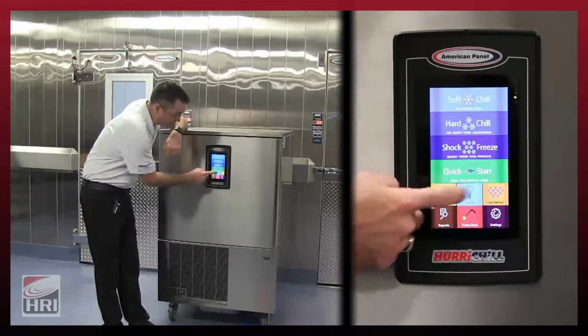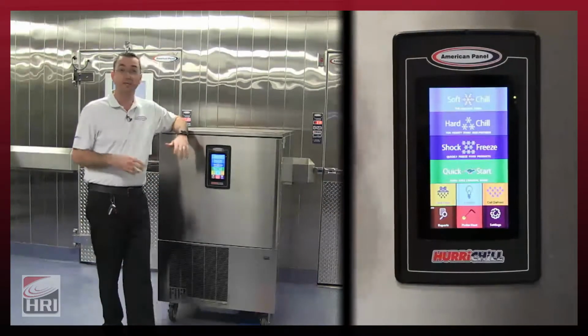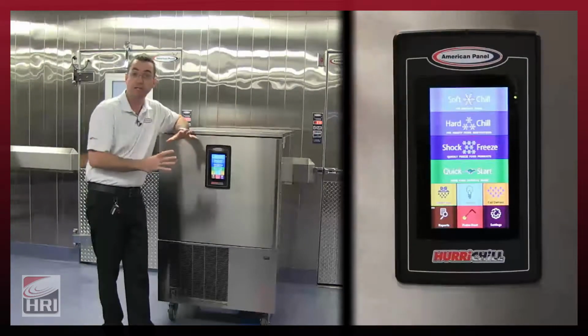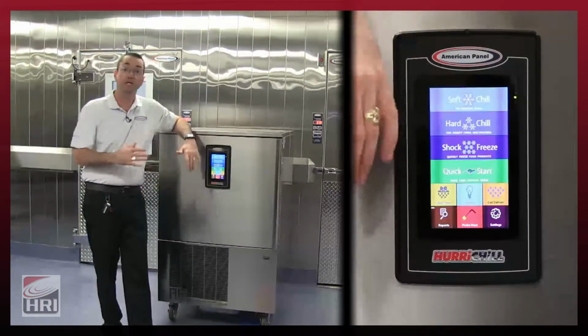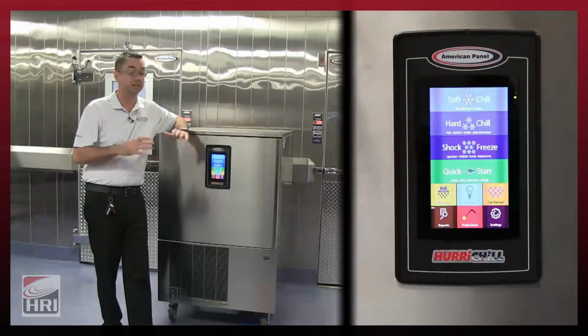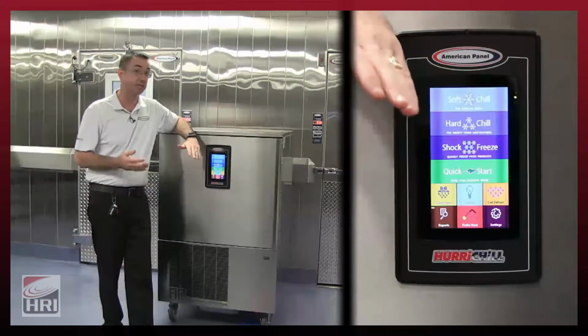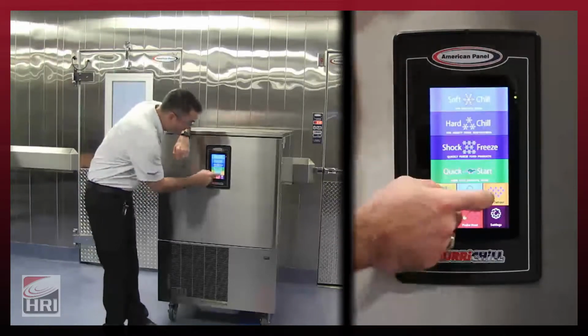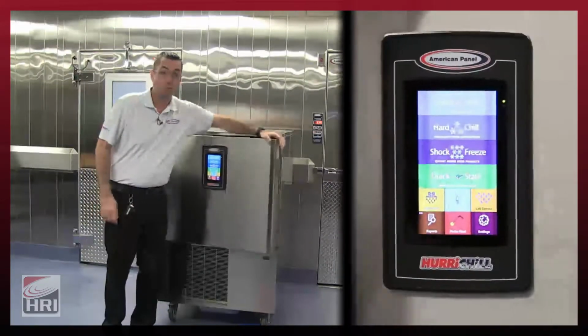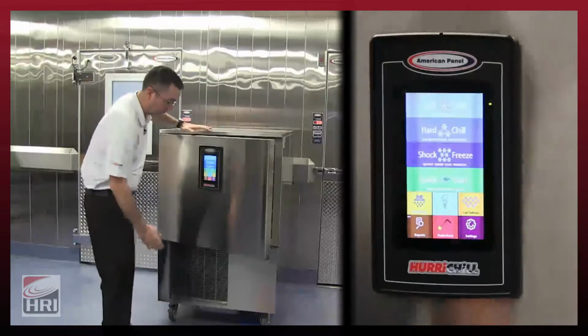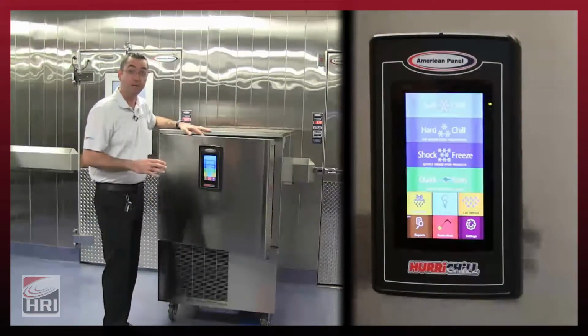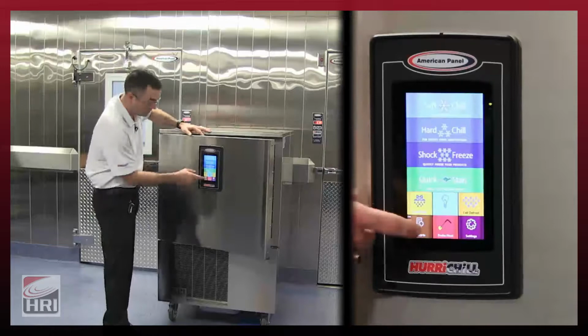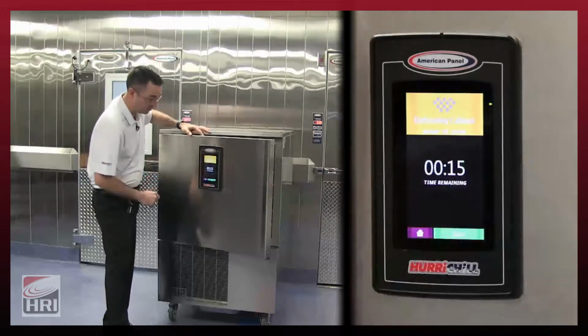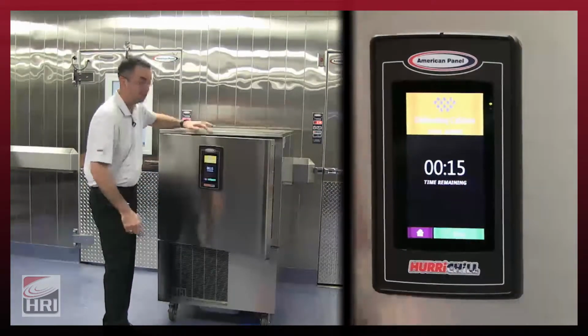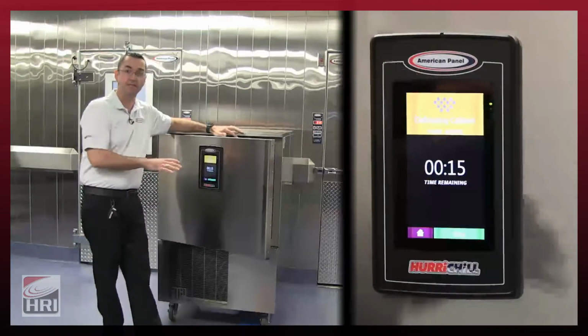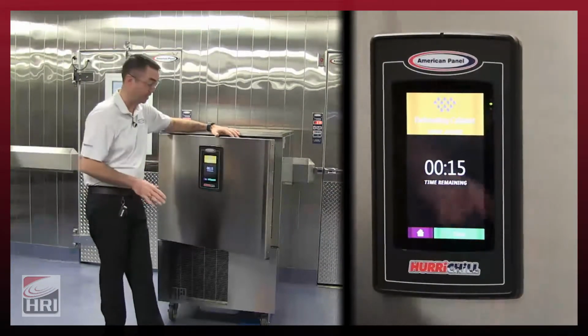The second option we have is sterilize option. At the end of the day, you wipe the cabinet down, you clean the coil, you clean the fans off, and you run that UV sterilization cycle. It's just an additional step in the cleaning process throughout the day to help promote food safety. Coil defrost. If you run a freezing cycle, this particular unit, we have a drain pan underneath, but you do need to run an air defrost coil cycle. If I hit coil defrost and hit start, fan turns on, 15 minutes later the coil's defrosted and I'm ready to run my next cycle.